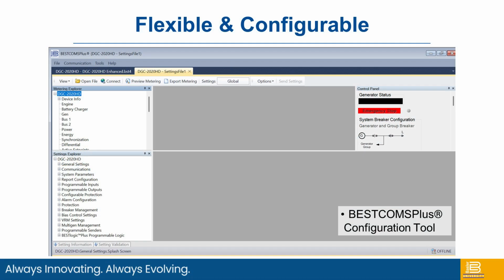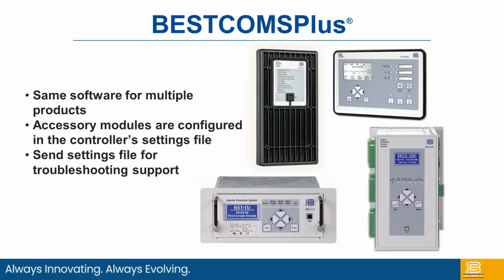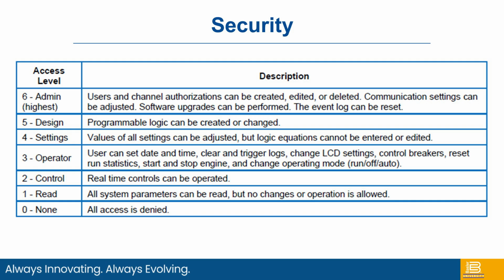Our BestCom software tool is extremely flexible and configurable, as I stated a couple of times. It's just a screenshot. The upper left-hand side is what we call our metering section. The lower left-hand side is our configuration screens. What's nice with BESTCOMSPlus software is that all of the Basler software and tools work with all of the Basler equipment. Towards the middle of the screen, the dark black is a DECS voltage regulator, an HD DGC up on the upper right-hand side, and then other voltage regulators and excitation systems on the bottom. There are 6 levels of security that can be put into the BestCom software. So if you are designing a system and you want to have limited access for, let's say, an operator so that he can't go in and adjust settings.